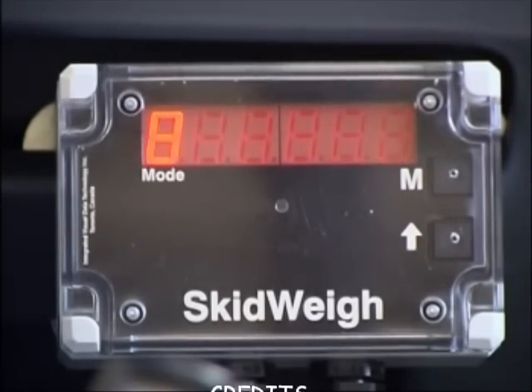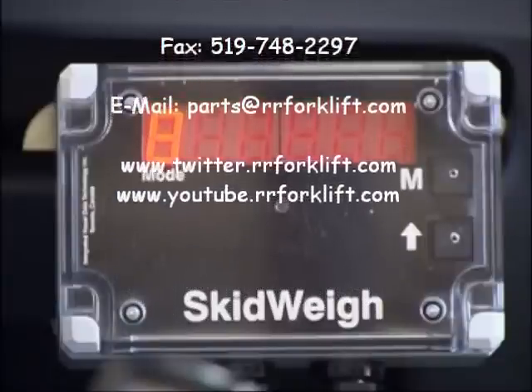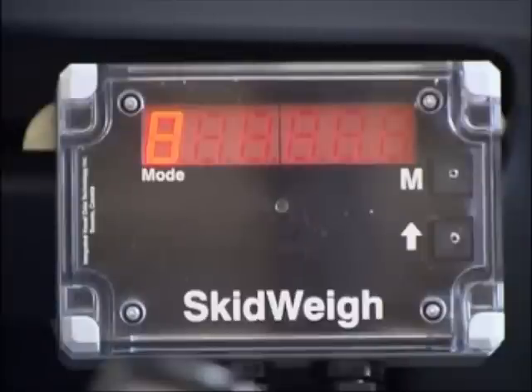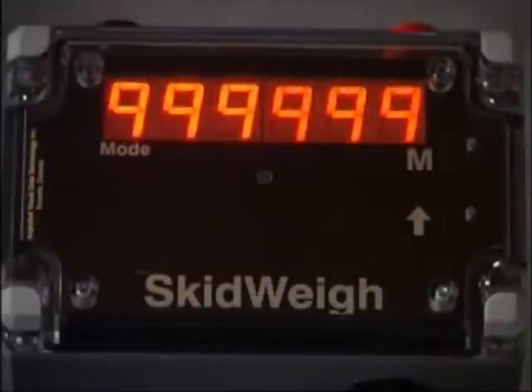On the right side of the display, you will momentarily see a software version number. For example, in this case, 85. And the display will automatically switch to number 8 on the left side of the display, providing there is no load on the forks. If a wrong connection is made to the pressure transducer's wiring harness, the display will show multiple flashing 9s across the display. If this happens, you must correct the error and start again.